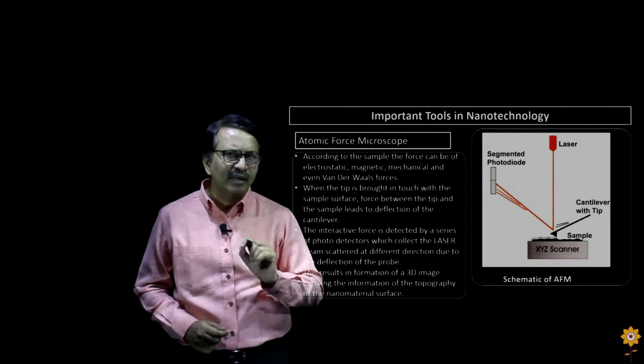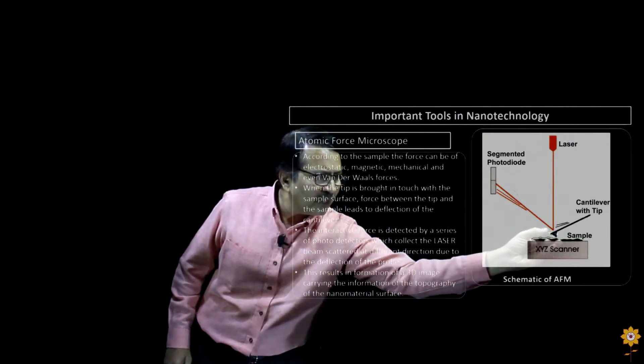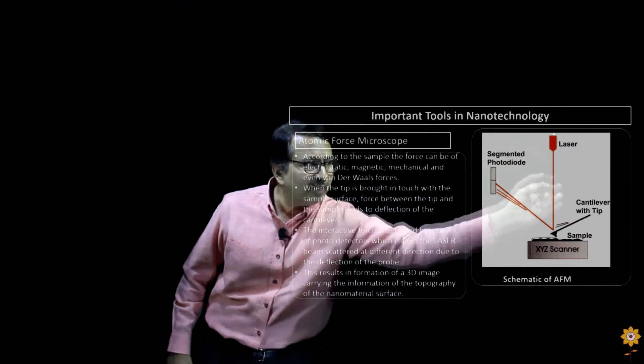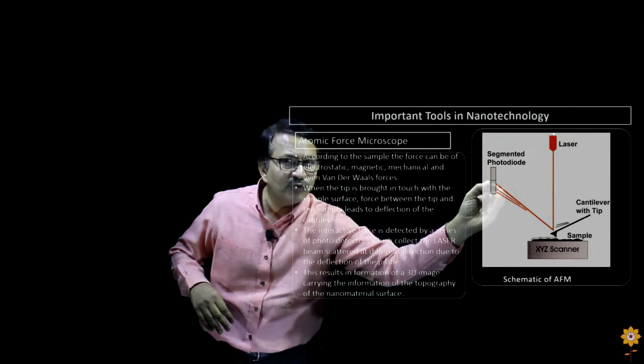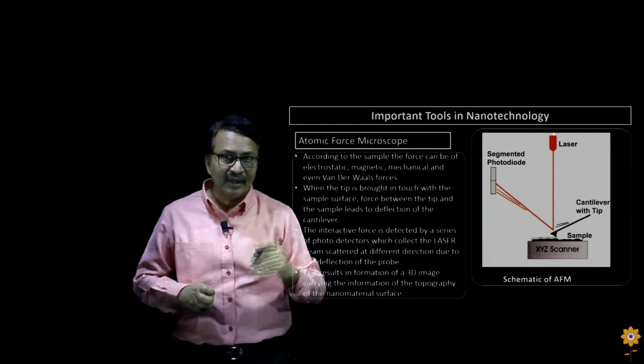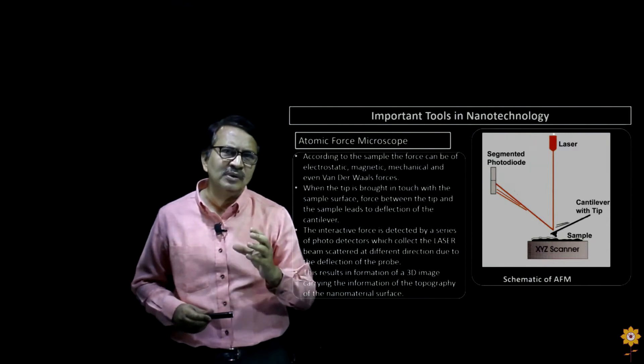Let us now see how an AFM functions. Here is a schematic diagram of an AFM. One of the basic components of an AFM is the cantilever tip, which scans the sample placed below it. Since AFM is an opto-mechanical device, there is a mechanical part — the cantilever — and an optical part: a laser beam that falls on the cantilever. As the tip moves, the deflections of the tip are captured by a series of photodiodes. These deflections combined with the XY scanner result in a 3D topography of the actual nano surface.